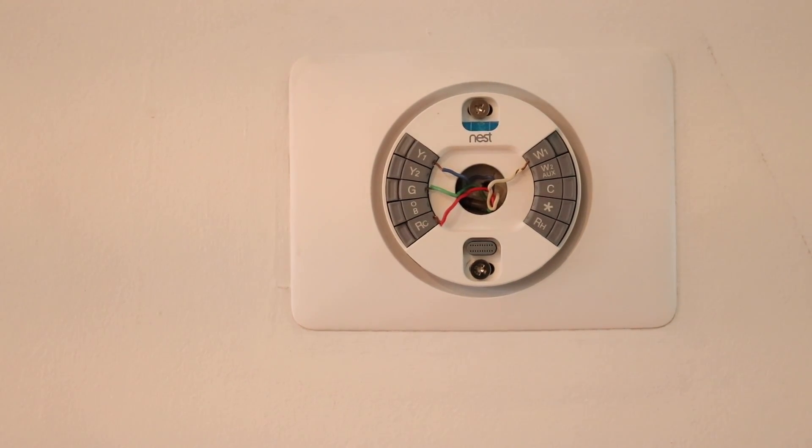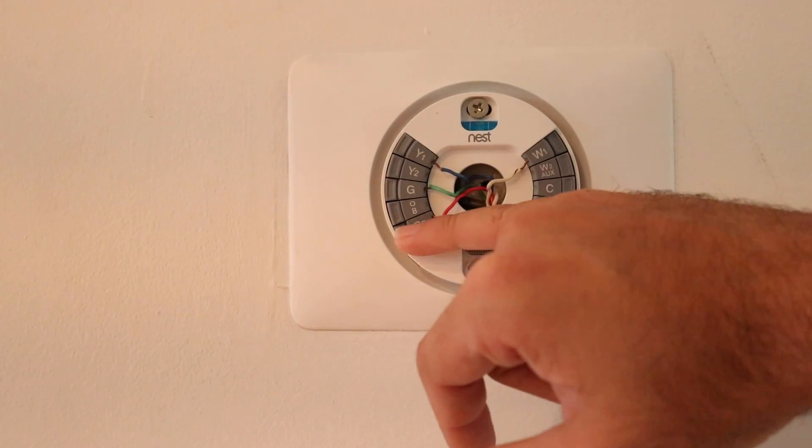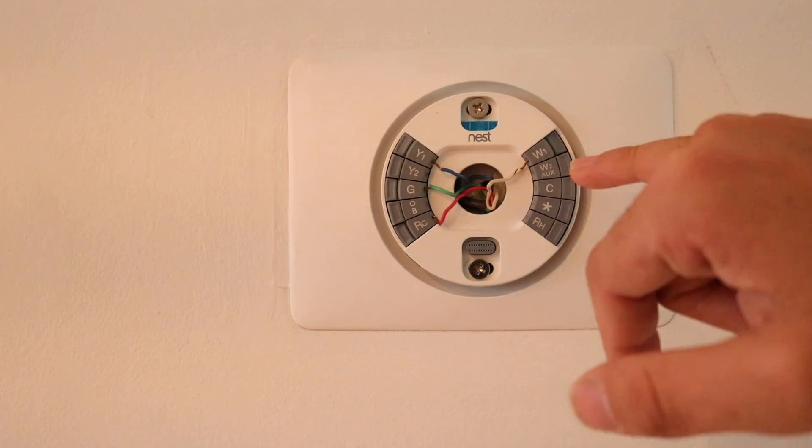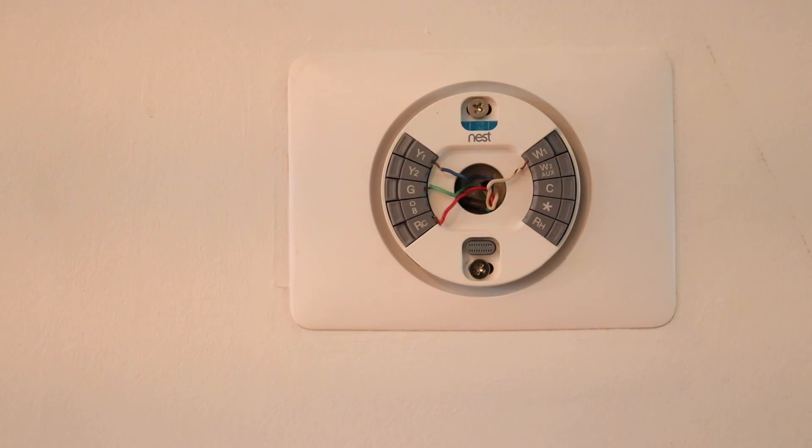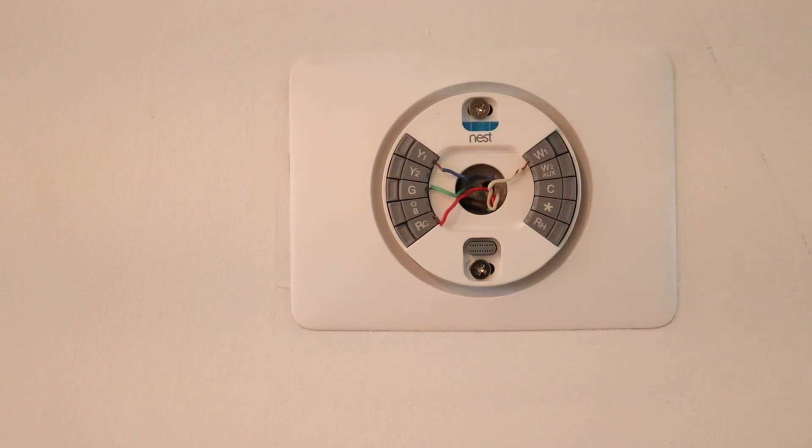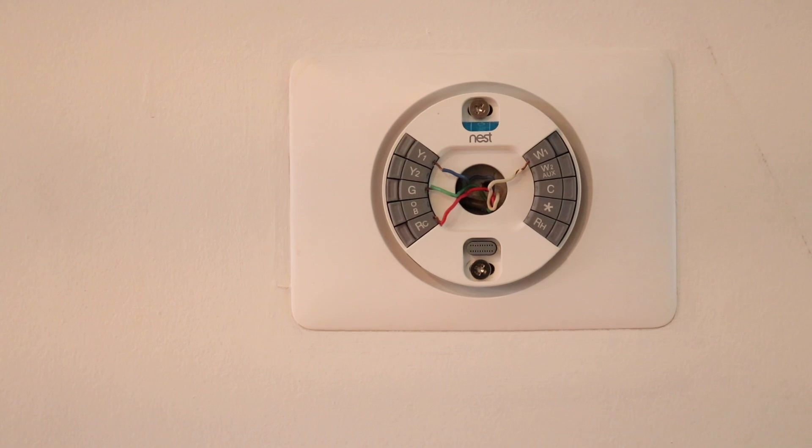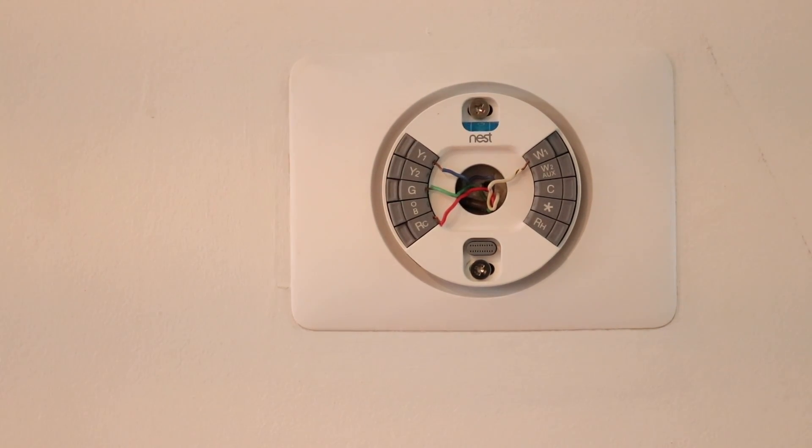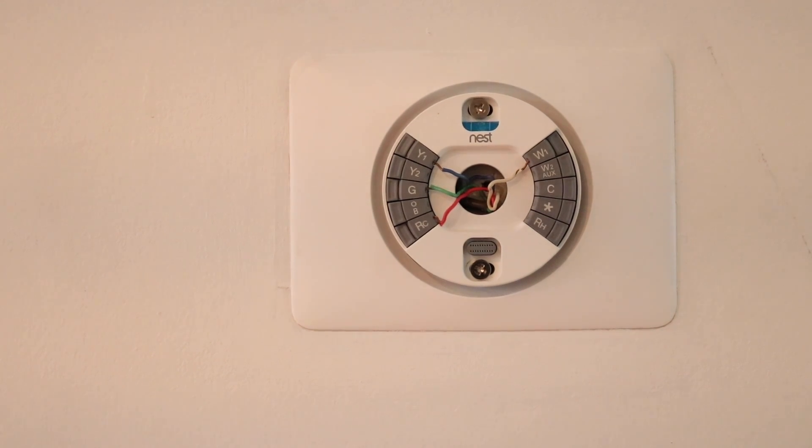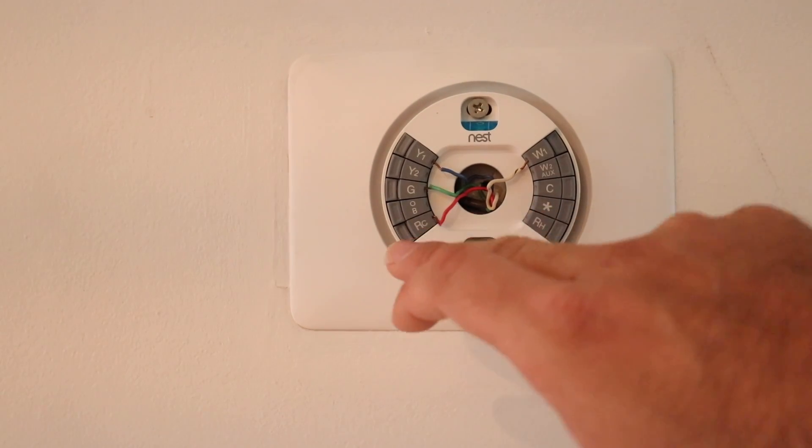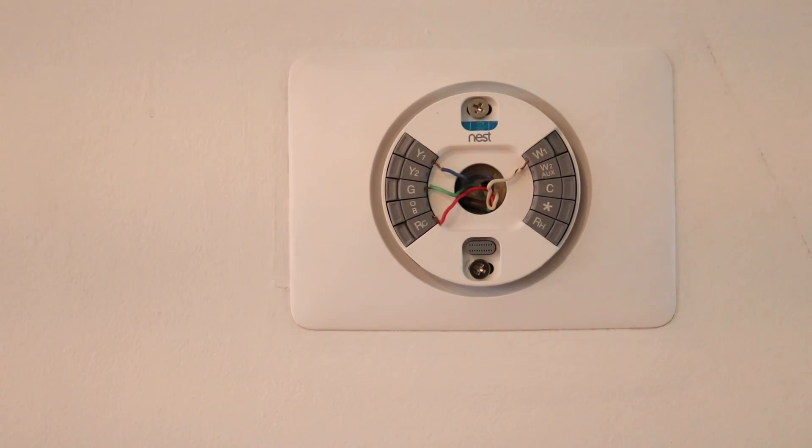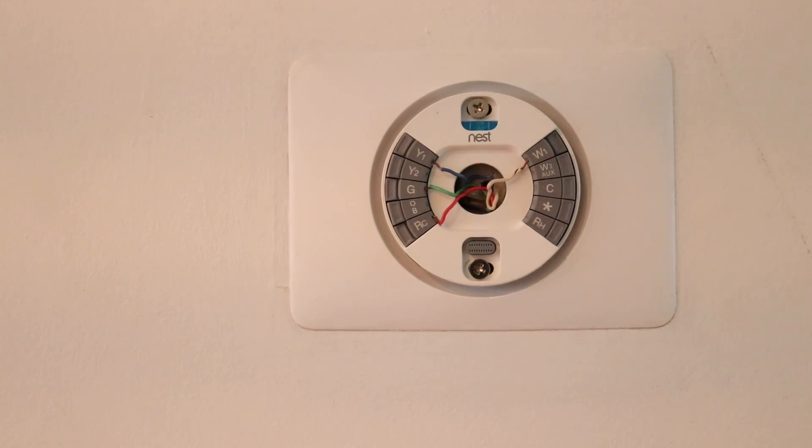Now modern heating and cooling systems that have a blower motor will automatically turn on the fan even if you don't have the G wire connected. So what we're going to do is we're going to take the G wire and we're going to use it as a C wire, the common wire. And what a common wire does is it allows a return current path from the power, the RC through the thermostat and back through the C wire so that the thermostat, the Nest thermostat can charge itself with the C wire. The problem is when you don't have the C wire, sometimes a furnace is not putting enough energy out or your furnace is too sensitive and will not let the Nest thermostat charge with the small amount of current that is going through it.